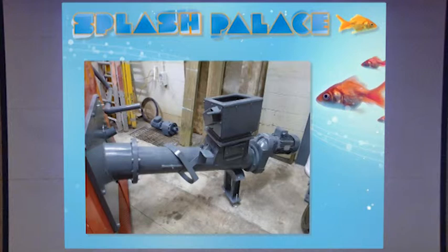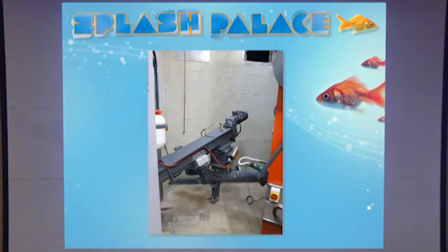This photo, you can see the stoker auger for the chip. And this is the extract auger connected to the stoker auger on the bottom. And another example of the sort of cunning engineering that this thing has, there's a white bucket here with a red lid on it. That's full of water. A sensor in the stoker auger opens a valve which floods the auger with water if it detects a backburn. So that's another example of some of the impressive engineering in this thing.